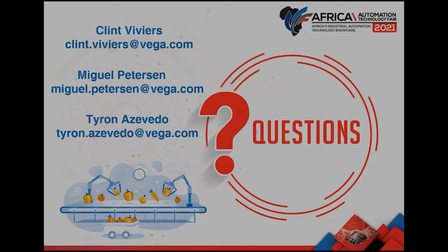Yes, that is possible indeed. The VEGAPOINT, as I mentioned earlier with build-up, has the same functionality where we've got a setup window based on the decay of the product. If you use water and oil for example, you tell the device that this is water, and then you tell it that this is oil, and it detects the product. That way you've got an interface measurement between oil and water. The device is also able to distinguish the emulsion layer from the actual product.